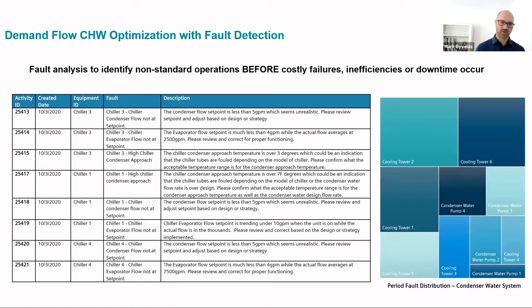In this case, for a chilled water system, we're applying fault detection and diagnostics to it. So you've got this big library of rules saying here's all the things that might go wrong in this particular system. It's always monitoring what's happening at a given time and letting building management know: we had this problem, here's when it occurred, here's where it occurred, here's a description of the issue, and some information about a resolution for it.